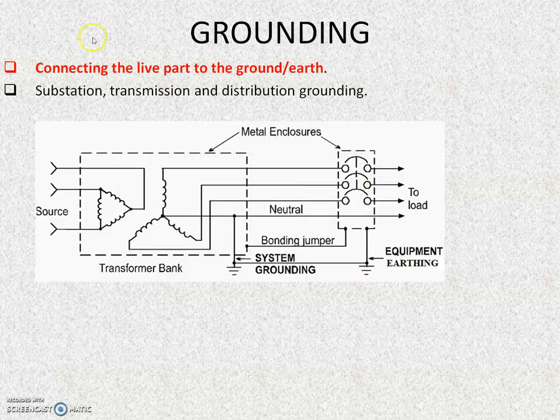Here we will normally be connecting the neutral points of the transformer bank to the ground, or the generator, and also the neutral connection is grounded. In the normal case, this neutral connection will not carry any current. Normal case means normal balanced condition. But during unbalance, a current will flow through the neutral and that will be grounded. It will be flowing through the ground.